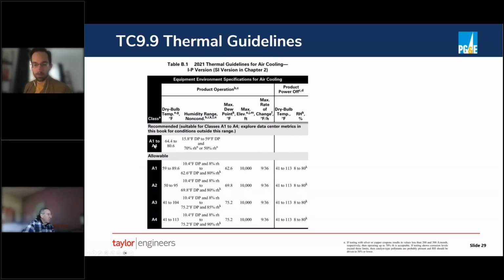So the recommended dry bulb is 64 to 80.6, but you're allowed to go down to 59 and up to 90 if you're an A1 versus an A2. You can go wider and wider and so forth. And I'm going to show this in a chart in a second. But one thing that's often overlooked in this is things like the maximum rate of change. As the load changes, as the ambient outdoor conditions change, you could have swings in the temperatures and so forth in your data centers.